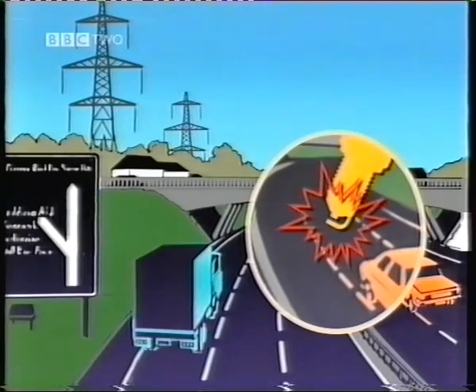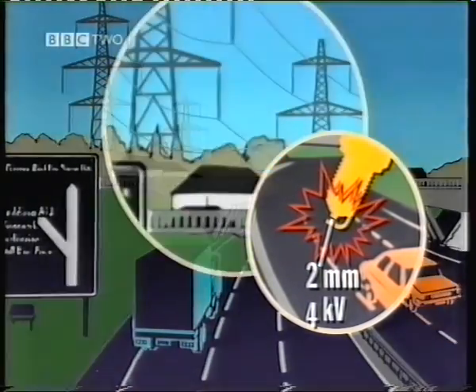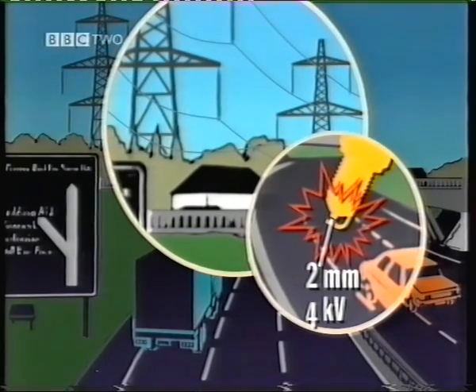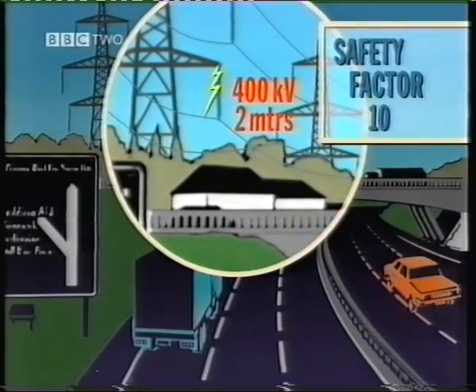In a car's spark plug, the gap at the bottom here is where the spark is formed. It's about 1 millimetre, and that needs at least 2 or 3 kV in air. Twice the gap would need twice the voltage to break it down and form a spark. Scaling up would suggest that 400 kV sparks could jump 200 millimetres or so. Put in an engineer's safety factor of 10, and we'd better not get within a couple of metres of one of the 400 kV lines. But that's with dry air. If it's raining or foggy, the insulation strength is nothing like as good, but you get the general idea.